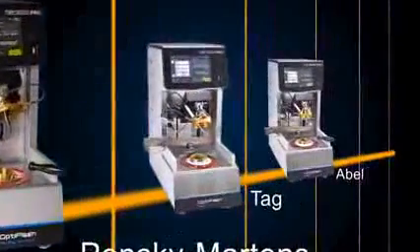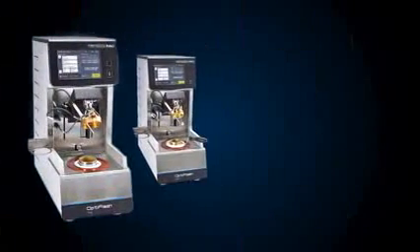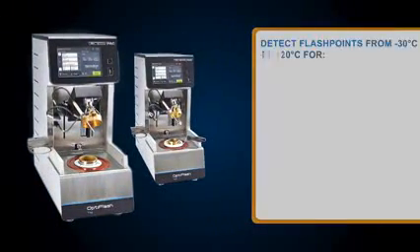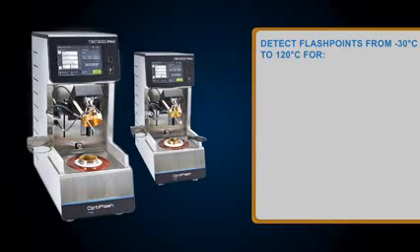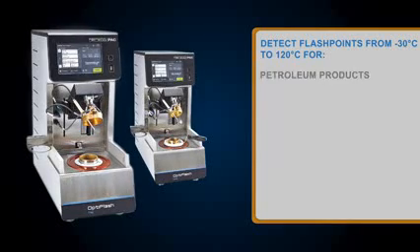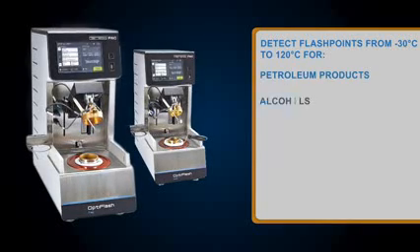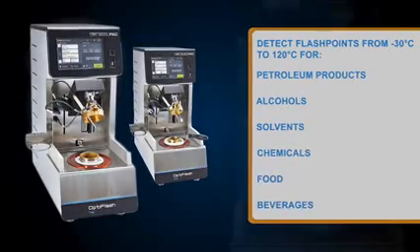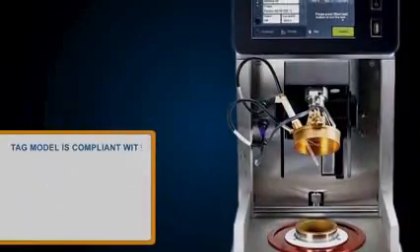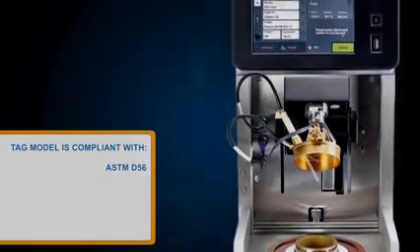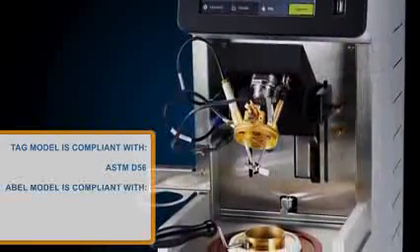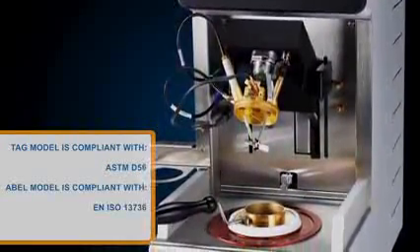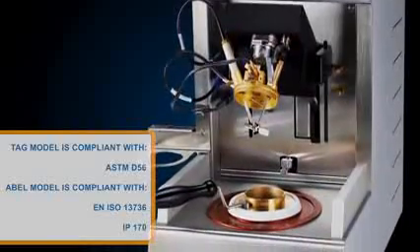The OptiFlash TAG and OptiFlash ABEL models accurately detect flashpoints from minus 30 to 120 degrees Celsius for petroleum products, alcohols, solvents, chemicals, food and beverages. The TAG model is fully compliant with ASTM D56. The ABEL model is fully compliant with EN ISO 13736 and IP-170.